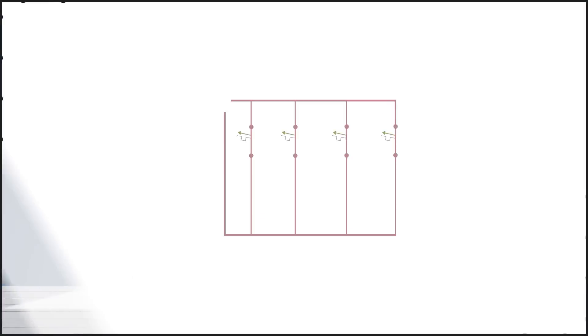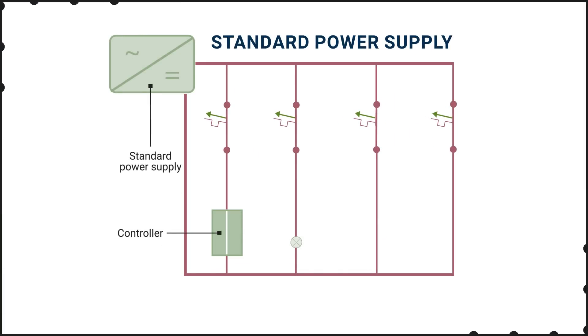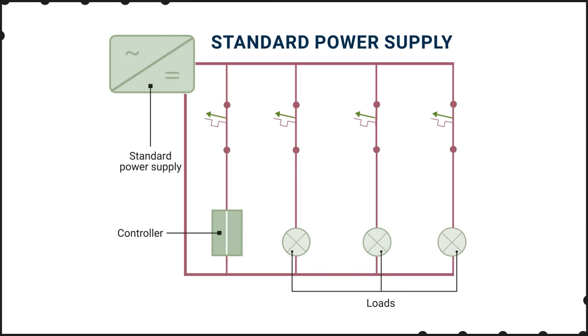Quint power supplies with selective fuse breaking technology (SFB) are designed to enable coordinated circuit protection on the DC power bus, preventing damage to other circuits and increasing overall system availability. Without coordinated protection, if one load experiences a fault, it can cause the power supply to trigger its own circuit protection, cutting off power to all loads on the bus, leading to expensive downtime for the entire system.